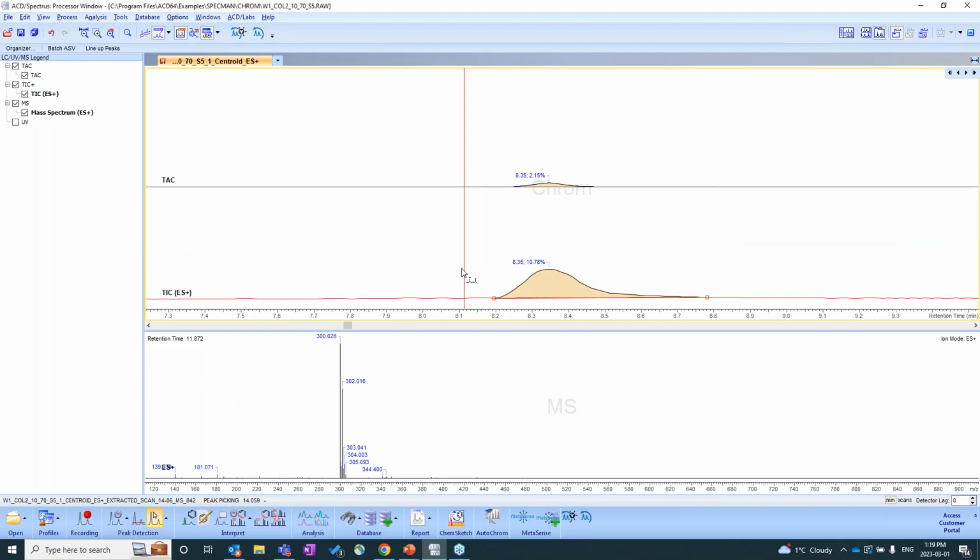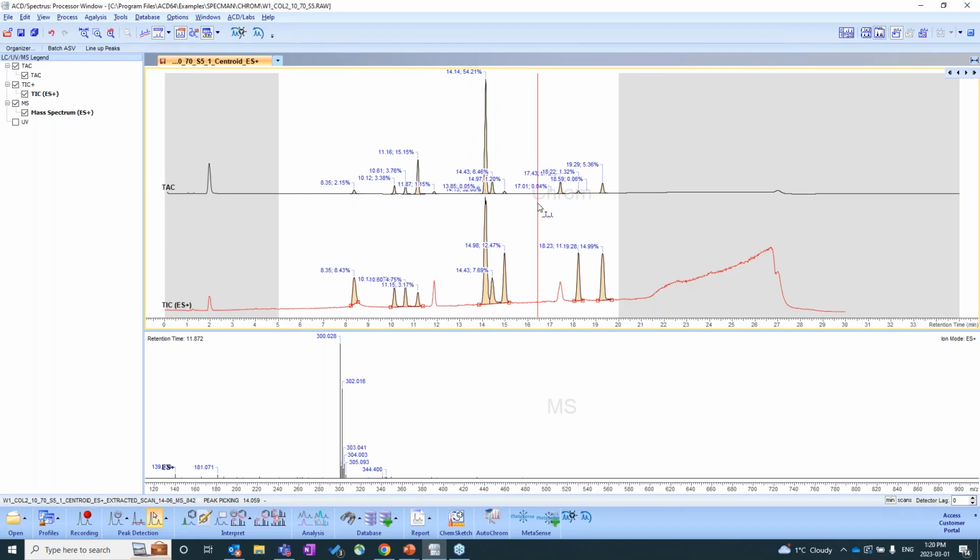What I wanted to show you with the peak by peak tool is that if I hover over this specific peak, we have this red box and these double arrows at the end of it. If I hover over that, I can click and drag and select how much of this peak I want integrated. So you can really start fine-tuning your data and what you want analyzed specifically. I'm going to zoom back out. And that is essentially how we go about doing this processing. I showed you the three methods: the automatic version, the peak level threshold version, and the manual peak by peak version.